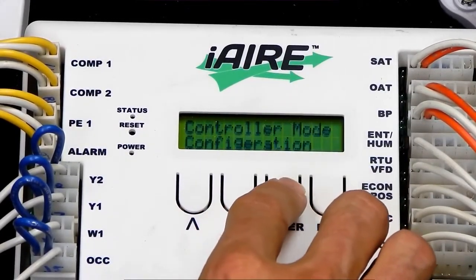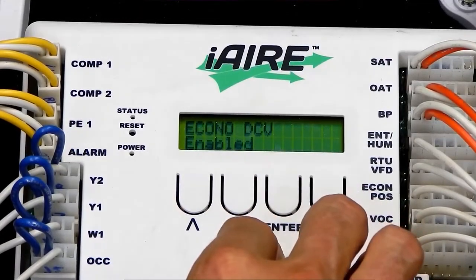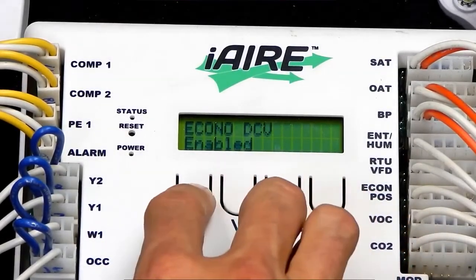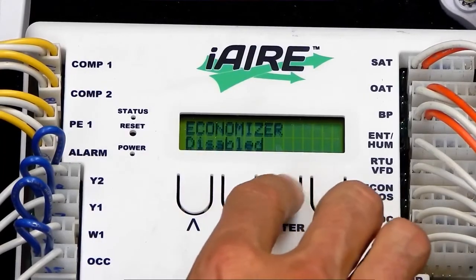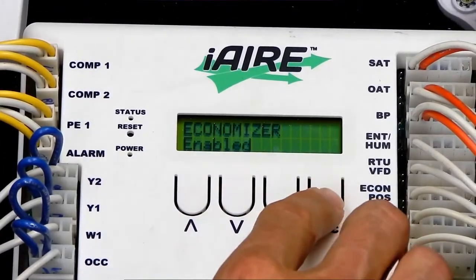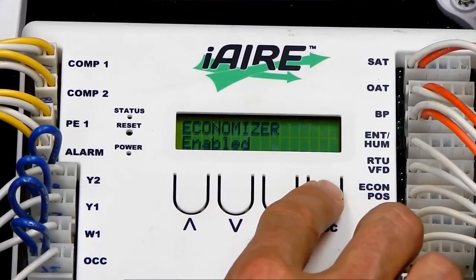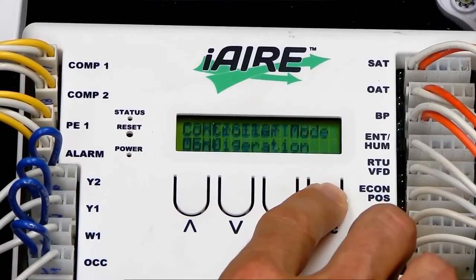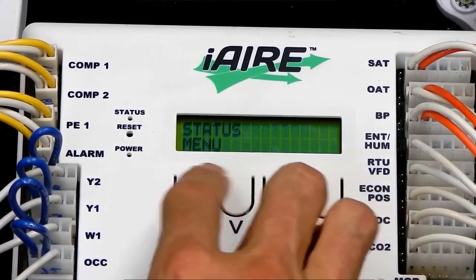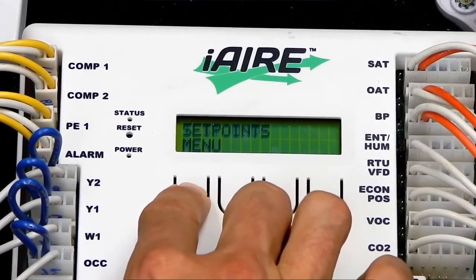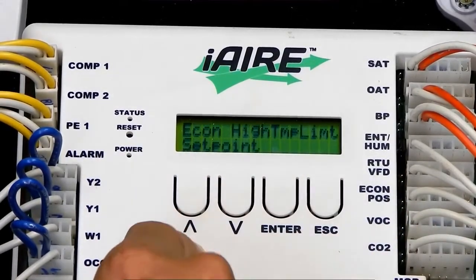The controller mode is which of the main modes it's in. Right now it's set to DCV. We will make it economizer. Hit enable. Now economizer mode's enabled. You're now in the standard economizer mode. The next thing you would do is go to the set points and make the set points that you want.